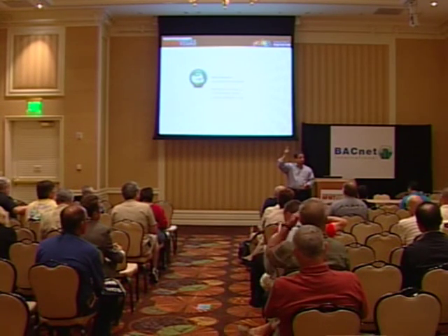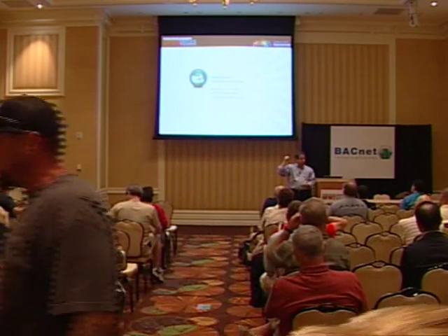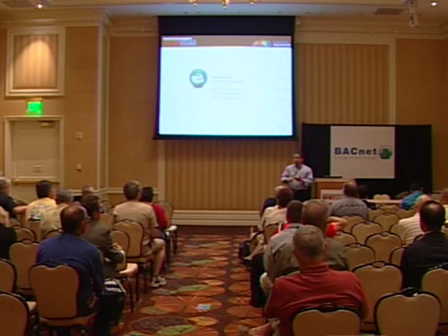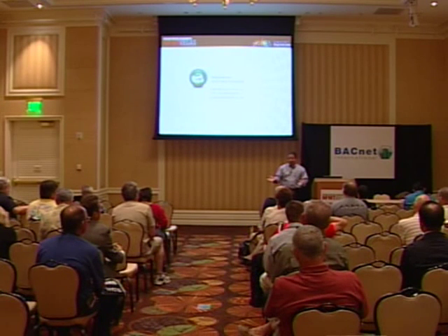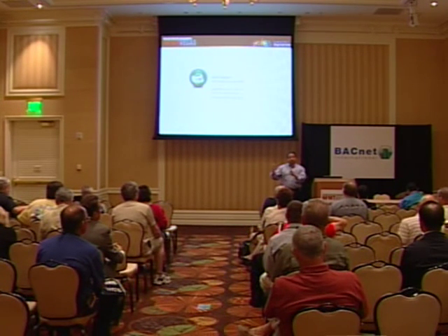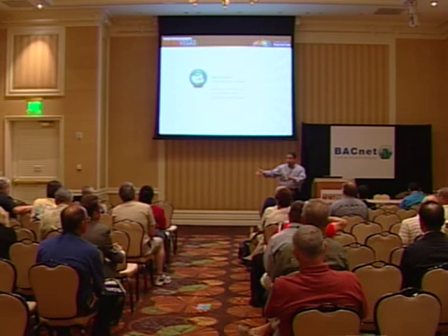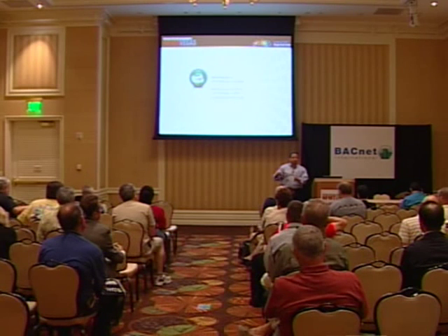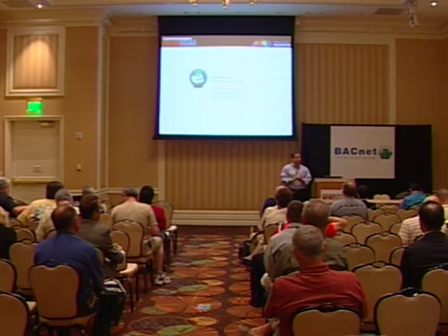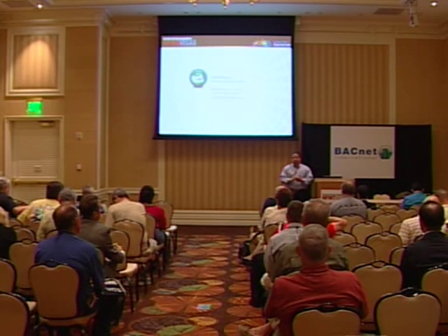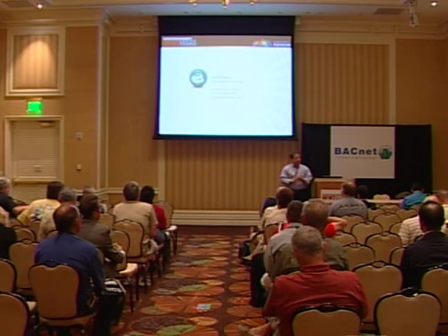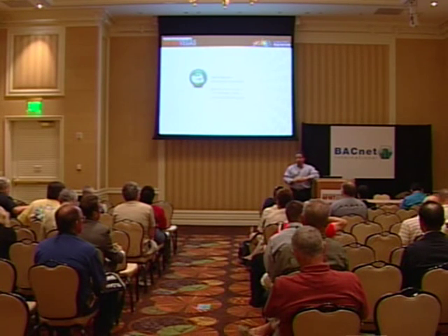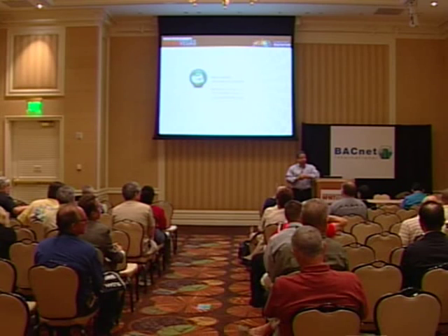When that ballast goes bad in the DALI world, who's going to replace it and make sure it gets the right address and programming back so it can go back into the system? I'm not saying bad things about facilities people, but I see them have a lot of difficulty maintaining what I already sell them, let alone something 10 or 5 times more advanced than centralized or distributed controls. In my opinion, you don't get a lot more energy savings out of addressable ballast technology. You can get some targeted things, but I'm not sure the payback is there for most customers I've talked to. So I don't know if that answered your question or not.